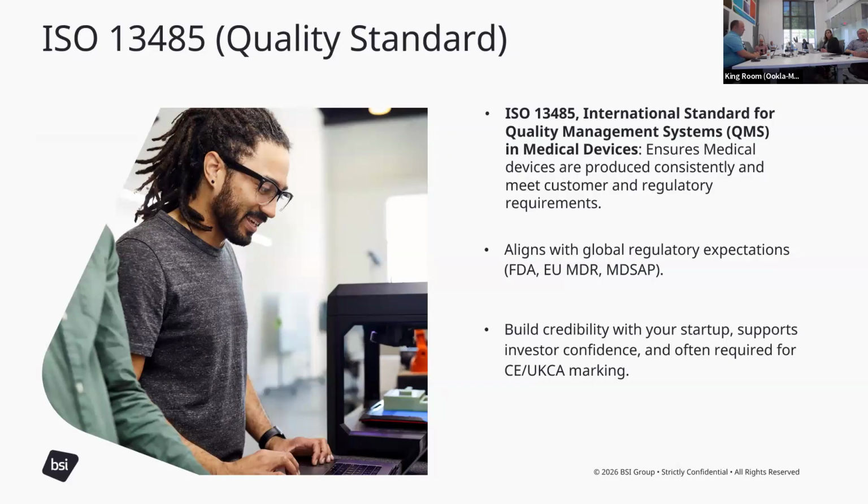So ISO 13485, if you look at any real device company, they are 13485 certified. A lot of you might have heard of ISO 9001. This is really the next step where it's a very device-specific certification. It covers usually design of the device. So if I'm reviewing a device that's a vascular device, I would want to know that the people making it have scope to design vascular devices. This is how you can prove that they have that scope.